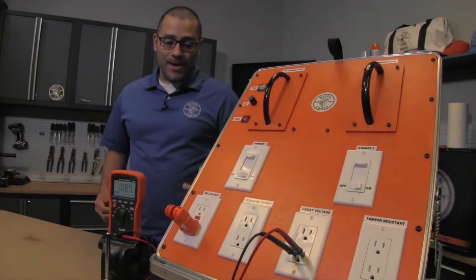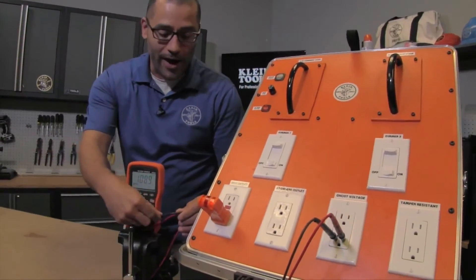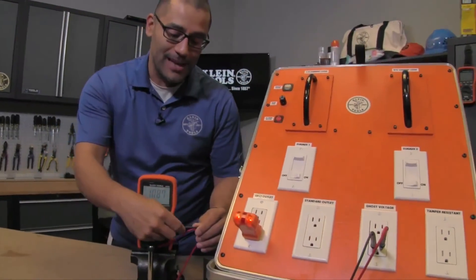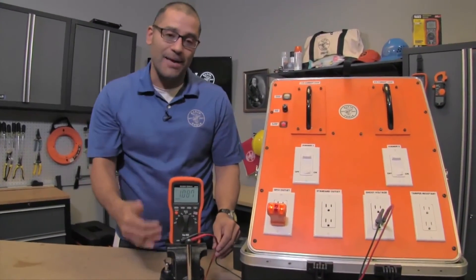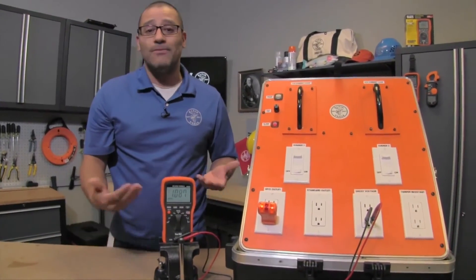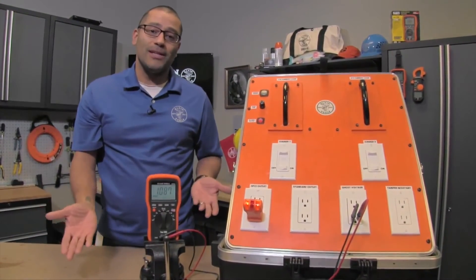Ghost voltage basically can be two wires running side by side where one wire has voltage on it and that voltage is actually induced into the second wire. So when you take your meter and hook it up and it's in high impedance it'll just read that voltage thinking voltage is there. However when you plug a load in you actually won't get the load to turn on.